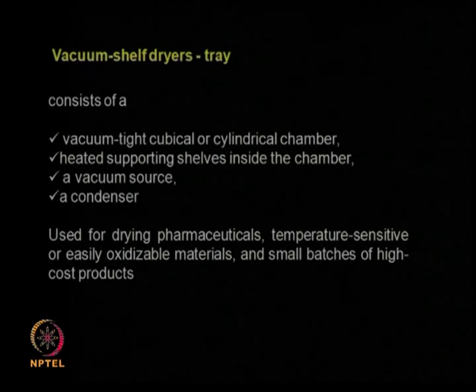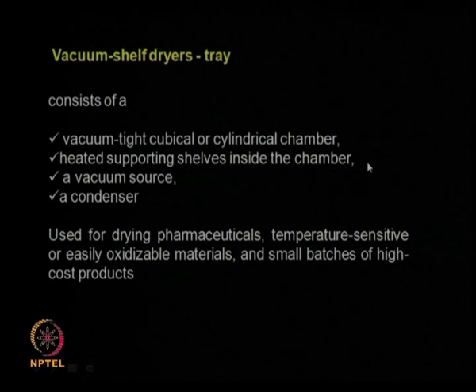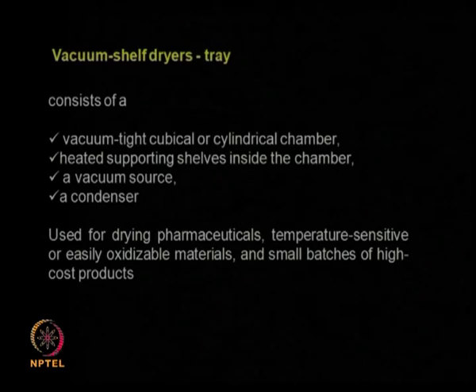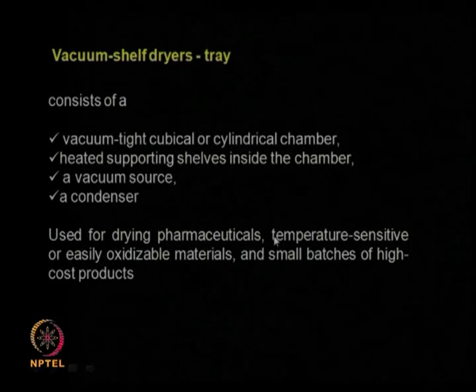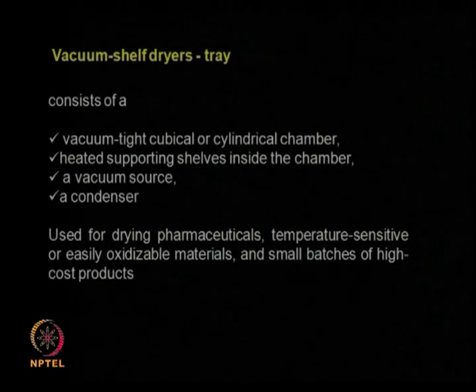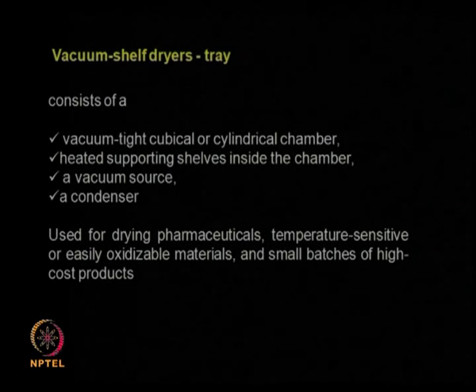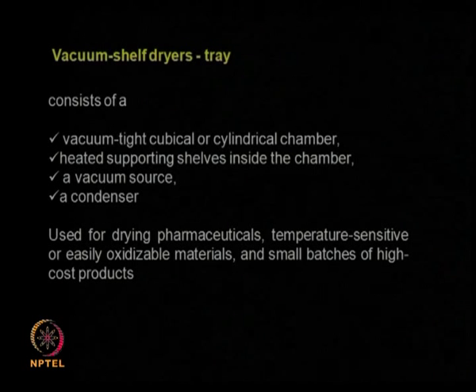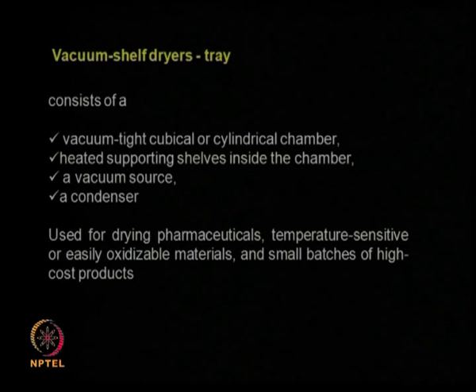The vacuum shelf dryer, also called a tray dryer, has a shelf with many trays inside a cubical or cylindrical chamber maintained under tight conditions because vacuum is applied. There is a heating source and a vacuum source, plus a condenser if you want to collect the solvent or moisture that evaporates. This is useful for drying pharmaceutical products and even temperature-sensitive products. We can use it for oxidizable materials because applying vacuum means no air inside, so no oxidation takes place. It is very useful for small batches and high-cost products because you have complete control over the drying process.